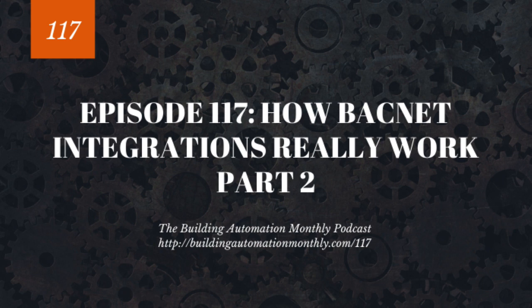But what do we address? That's a strategy decision we have to make. We can put a higher address. We could put maybe 35 or 36, depending on what controller address we did last. Realize that it's going to slow your trunk down a little bit, not a ton, but a little bit. And it's going to make troubleshooting a little bit more difficult.